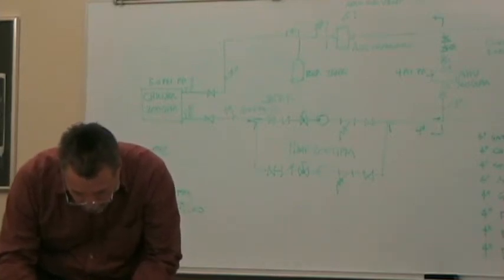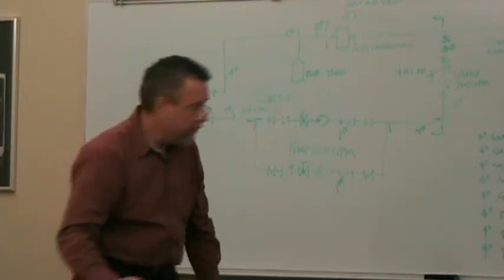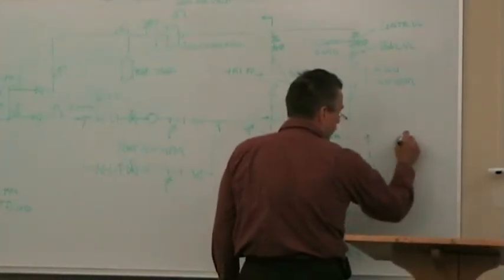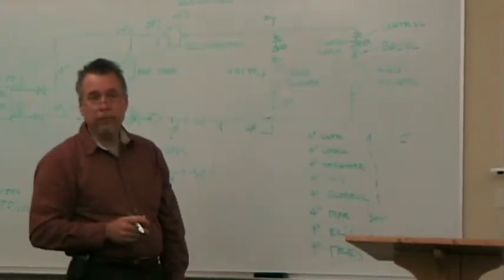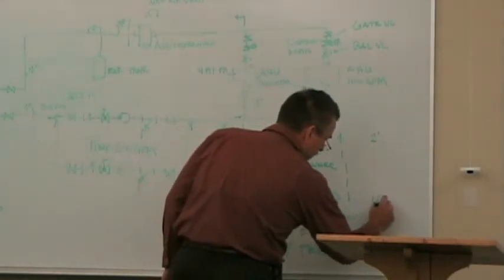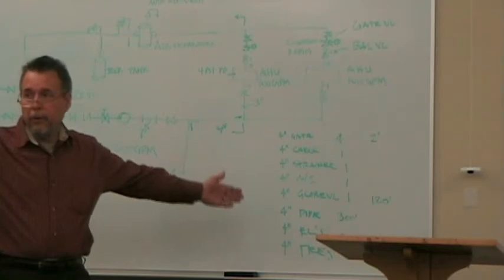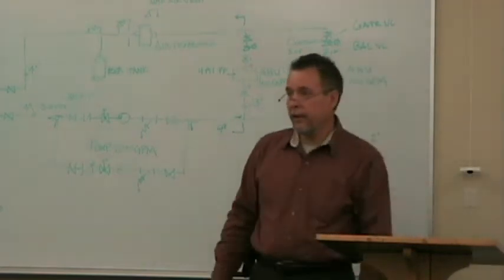Okay. So a 4-inch elbow, 4-inch straight open gate valve only has 2 feet of equivalent pipe. That's all it is. A globe valve, fully open, has 120 feet of equivalent pipe. What's the makeup of a globe valve? The globe valve, like our standard control valve, is a globe valve. Why? Oh, I see, just because it's not a fully open line?